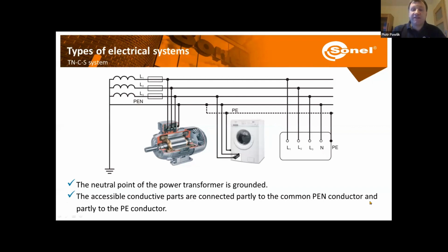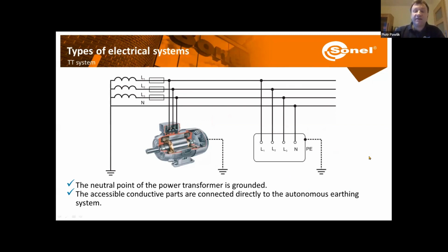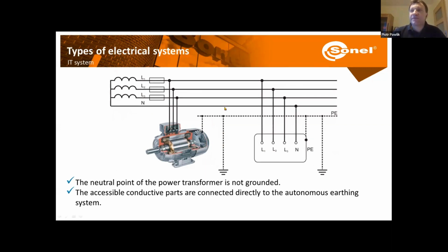And there's a sort of a hybrid, the TN-C-S systems. Once we look from the side of the power supply, from the transformer, first we have one channel called PEN, so protective neutral channel, which is later separated into neutral and protective channel. And additionally, the protective channel has to be grounded directly to the earth at some point. Okay, now other systems, that's the TT system. Here the central point of the transformer is grounded, and the conductive accessible parts of different devices are also grounded, but locally. So here the PE channel does not go through the transformer, it just goes locally to the ground. And there's also the IT system. Over here, the transformer is insulated from the ground. And if we have any accessible parts or covers, they are grounded locally. Now, there might be different IT systems with or without neutral conductor.